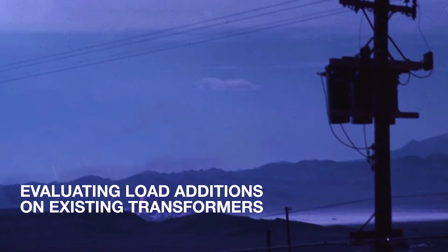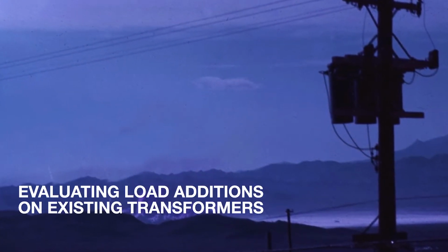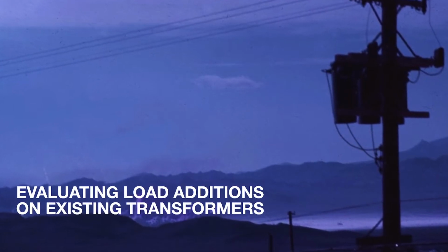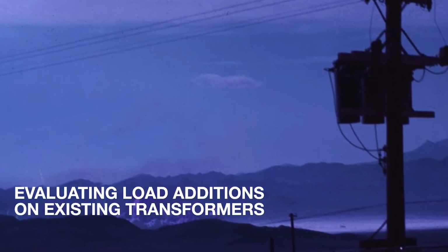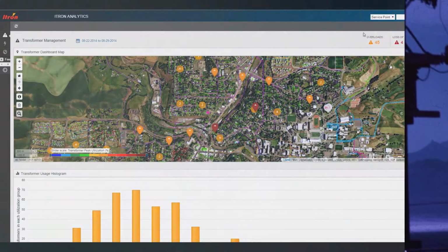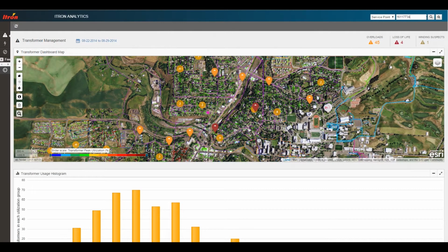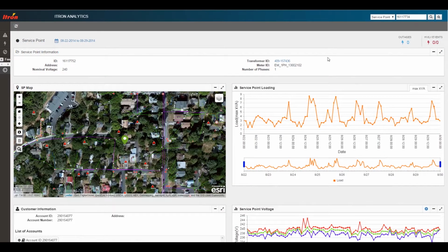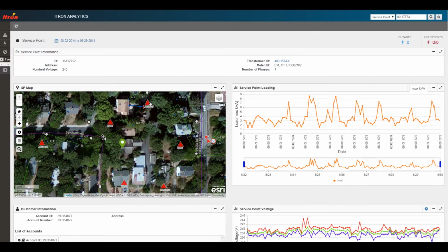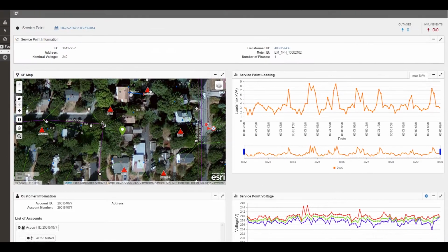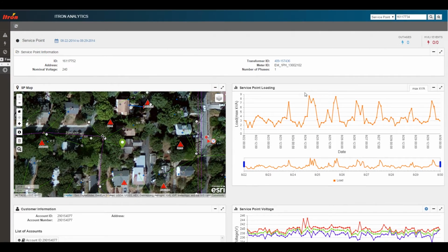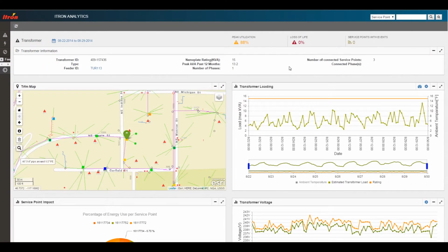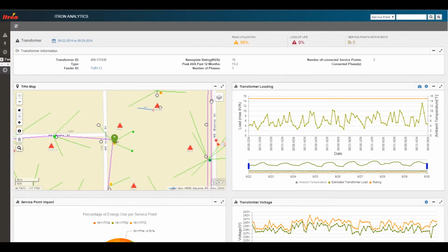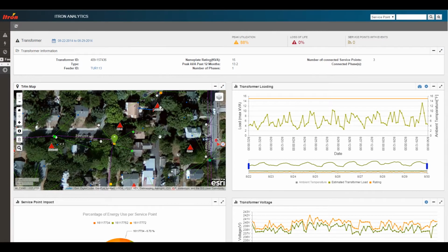In this scenario, we're evaluating the impact of additional load on an existing transformer. The customer intends to add load at their residence and has called a planner who will now investigate the request. From the system-level dashboard, a planner can view a summary of voltage, load, and outage information for the premise. To investigate a specific service point or transformer, the analyst enters the ID from anywhere in the application. The planner can view the account in question and its relationship to neighbors and the electric circuit. Load and voltage profiles are shown for any period of time, giving the planner historical data to consider.